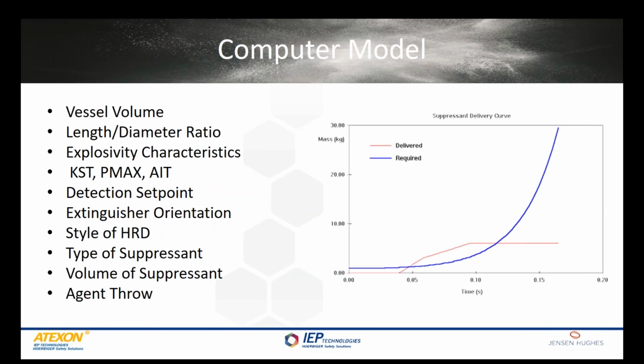Explosion suppression systems are a bit different than fire suppression systems. Most fire suppression systems use a volume versus concentration design methodology. With explosion suppression, the science is quite a bit more advanced than that. There's a lot of things that can affect whether an explosion suppression system will work correctly and be able to put out an explosion within a given threat. Certainly how fast the explosion is going to grow within that vessel. Martin discussed earlier how a high L over D, or length over diameter ratio, vessel is going to have a much more intense explosion than something that's more of a box or a sphere. So that's taken into account.